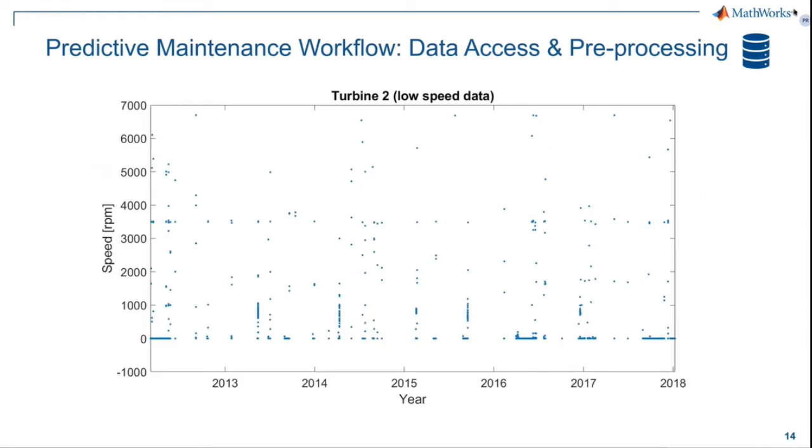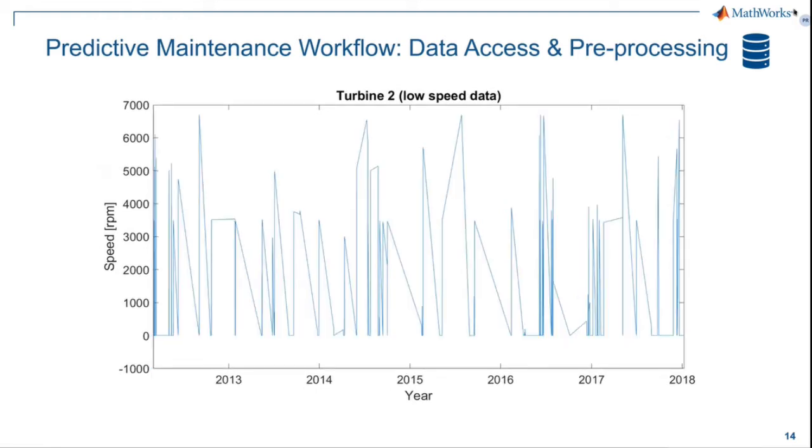After even more conversations with Peter, poor guy, he pointed out the turbine speed behavior when it's undergoing a wash. In order to show that behavior visually, we plotted the scatter plot as a line graph. This red line represents a time when a wash occurred, and I'm simply going to zoom into the circled area to give a better view of the turbine behavior.